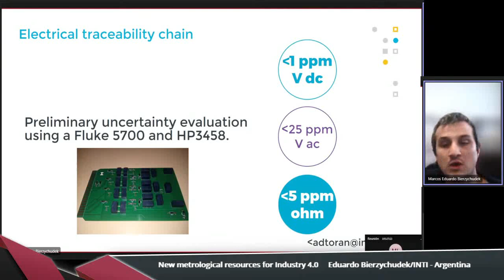This was a test under the table. The error with and without the board was, in DC voltage, lower than 1 ppm; in AC voltage up to 20 kilohertz, lower than 25 ppm; in resistance, in all the scales, lower than 5 ppm. We expect to have better results when we have the final system installed.